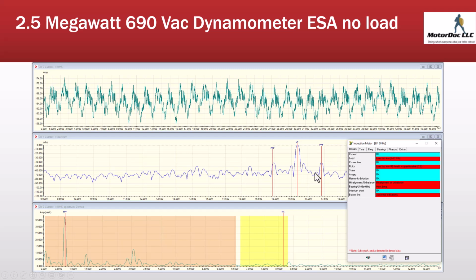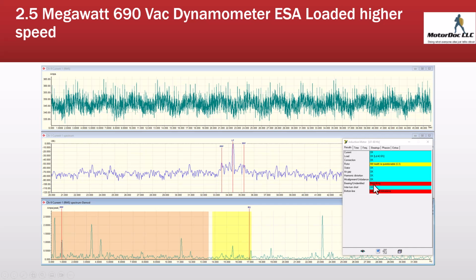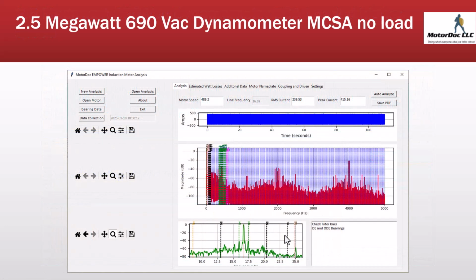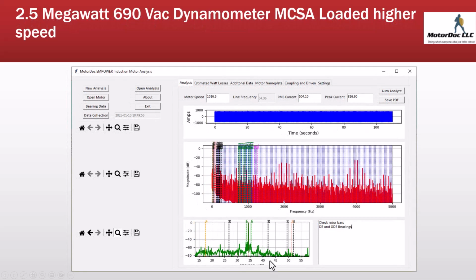You can see a rotor bar related issue, which turned out when we inspected it to be bad brazing, something that should be taken care of, but not the reason we were called there. As we took a closer look, you can also see that there's a bearing issue going on. So we looked at the frequencies associated with the bearings and found out that they had a drive-end bearing issue in particular that was causing problems. And you can see in current signature the exact same type of signature here, and so on. Okay, and again, under higher speed, the same thing shows up again.